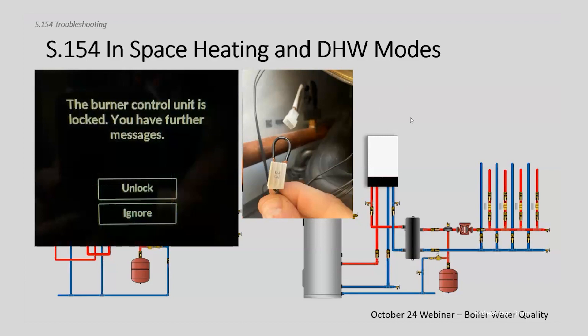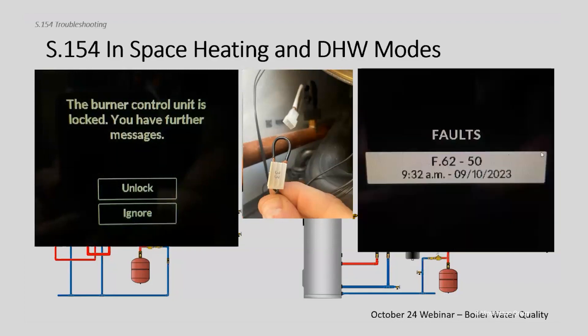Or you might come up with a fault — you might hear some percolation or kettling in the boiler, and then you get fault message F62 (the fixed high limit was tripped). This is telling me the flow switch was actually doing its job — you didn't have enough flow through the boiler for the flow switch to close. By bypassing it, you've tripped the operating limit or fixed high limit because you actually had no flow in the boiler. This would be different troubleshooting altogether — now we check the pump, is it overamping, things like that.